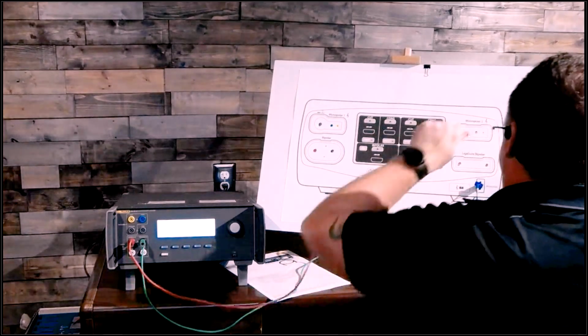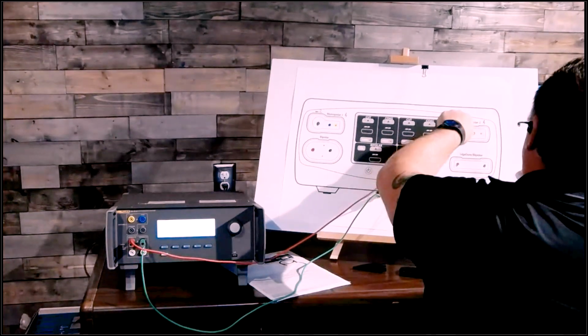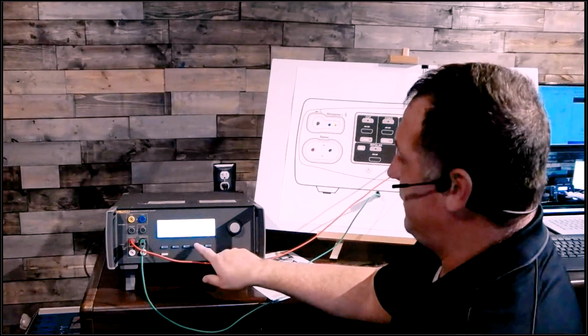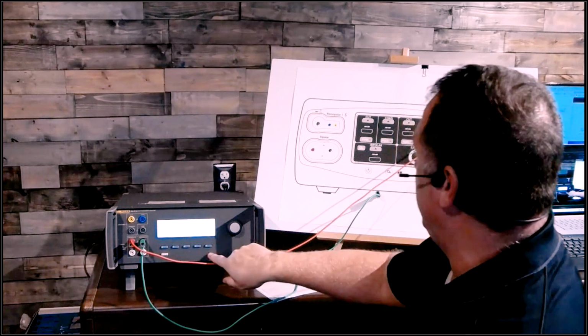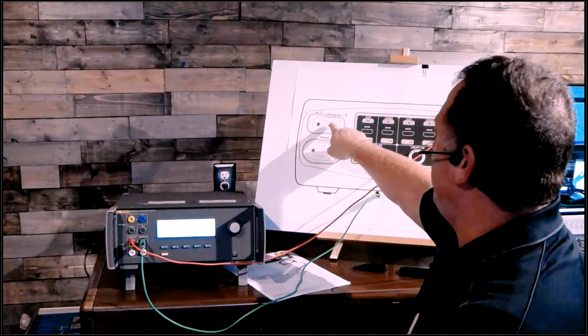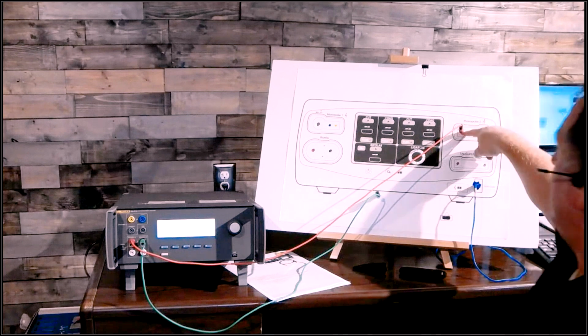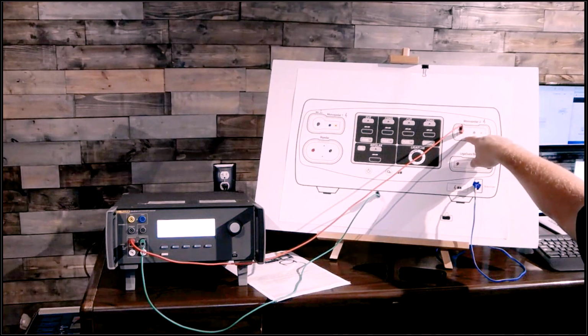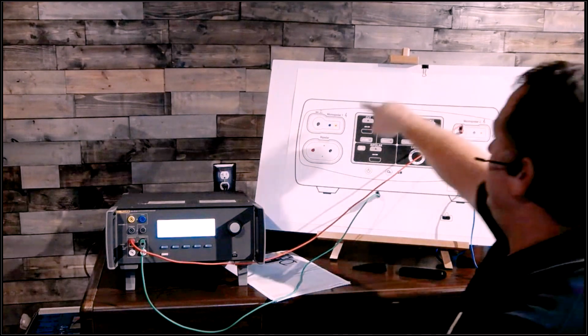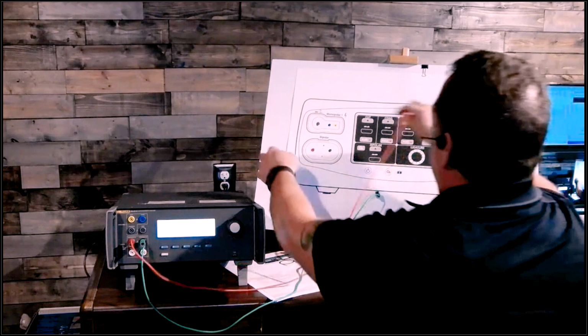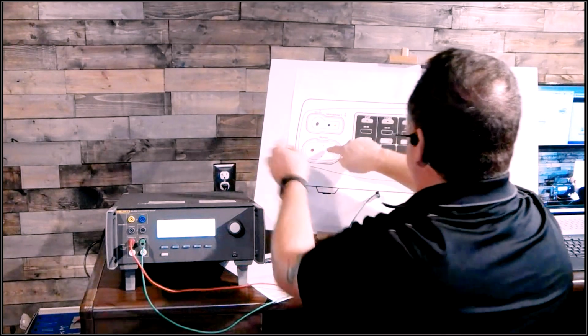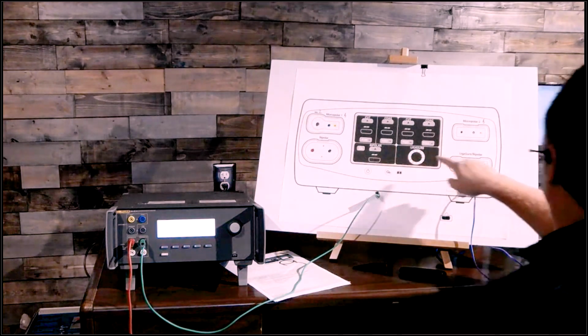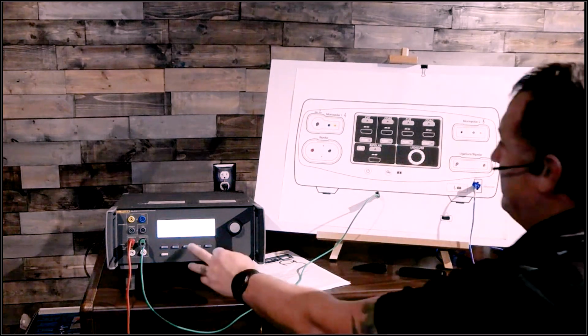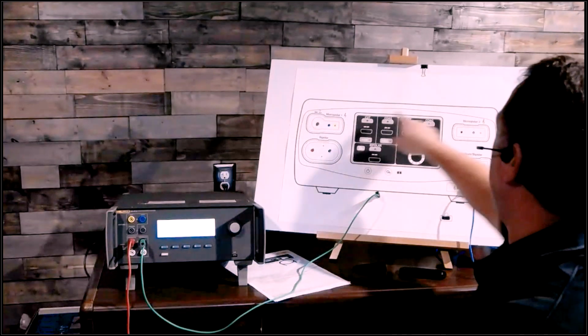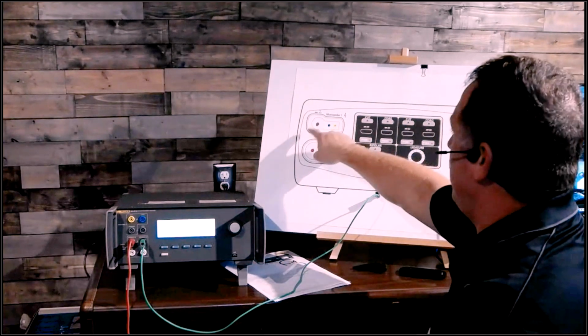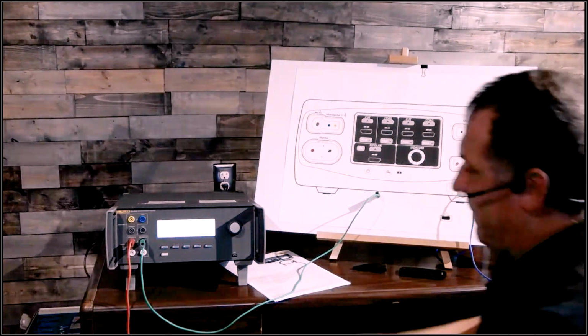Activate monopolar 1 and make sure you have less than 150 milliamps coming out of monopolar 2. Then deactivate your ESU, move down and check the bipolar ports to make sure no energy is coming out of bipolar, and none out of LigaSure. Then it'll probably have you move over to monopolar 2 and check these ports.